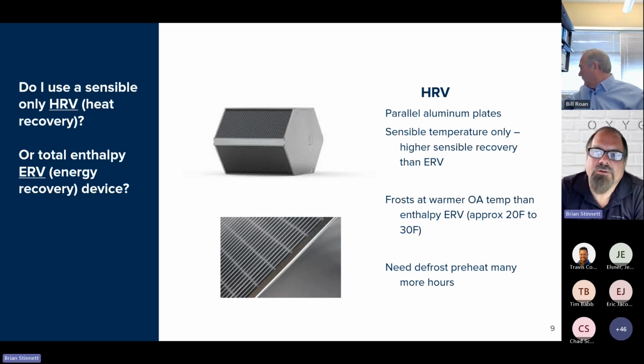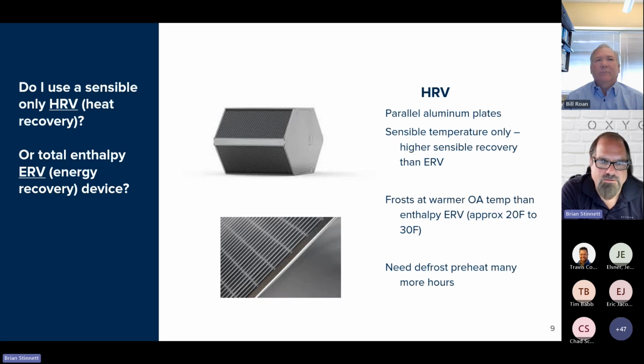If we think about plate heat exchangers, we have to ask the question: do we want to use an HRV, a heat recovery ventilator, which is sensible only, or do we want to use an enthalpy device, transferring both temperature and moisture? Commonly, in cold, dry climates like Denver, the first answer that comes to people's minds is, well, it's a dry climate, so I don't need moisture transfer. I'm not trying to do a job in Texas or Louisiana where it's high humidity. The thing to think about there, though, is that a sensible-only heat exchanger is comprised of aluminum plates. Those aluminum plates are going to start developing frost at around 20 to 30 degrees outside air temp, depending upon how much moisture is in the exhaust air. So Denver, with a design condition of 0, I would be spending a lot of hours running a preheater, whether electric or hot water or whatever, to make that incoming outside air no less than the frost temp, which again would be between 20 and 30 degrees.